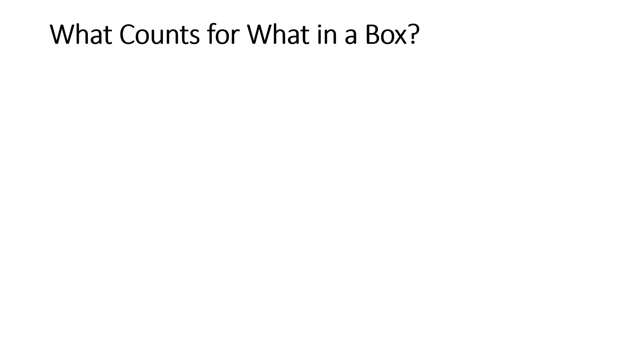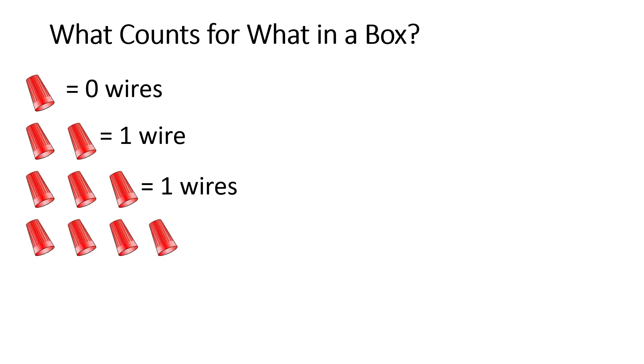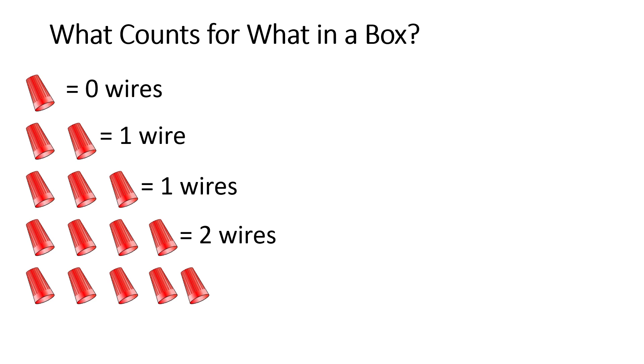The first thing we're going to take a look at is what actually counts towards box fill as far as conductors. Obviously the conductors themselves, but there's all the additional stuff that gets stuffed inside those junction boxes that we need to take into consideration as well. The first thing we're going to look at is wire connectors or wire nuts, better known as marrettes. Wire nuts or marrettes are counted in pairs — one individual wire nut doesn't count towards box fill. As soon as we have a pair, that counts as one wire. Three wire nuts still only gives one true pair, so that still counts as just one wire. Four wire nuts gives two individual pairs, counting as two conductors. Five wire nuts still only gives two full pairs, so that still counts as two wires towards box fill.